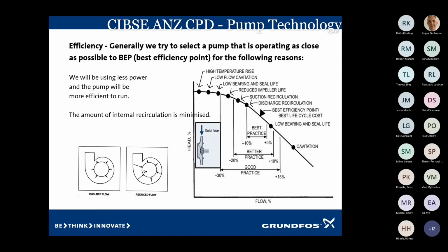As you can see at the top end of the performance curve, we start to generate high temperature, a little bit of cavitation, and a low loading on the bearings. You're also going to get a lot of noise up that top end there, especially if you've got a big pump trying to punch a lot of water out. It will become really, really noisy. All of that will tend to end up reducing the service life, the lifespan of the pump.